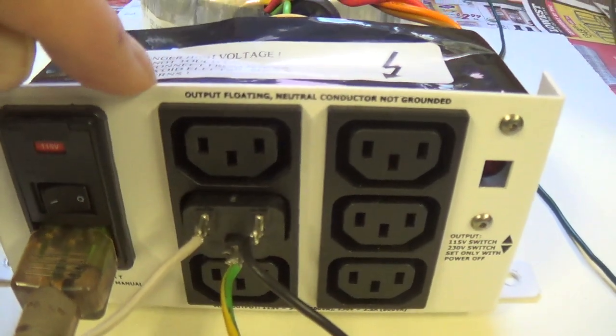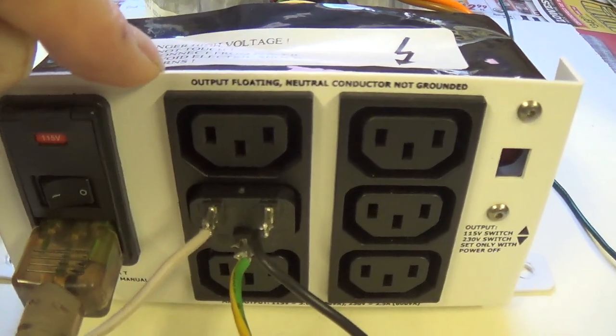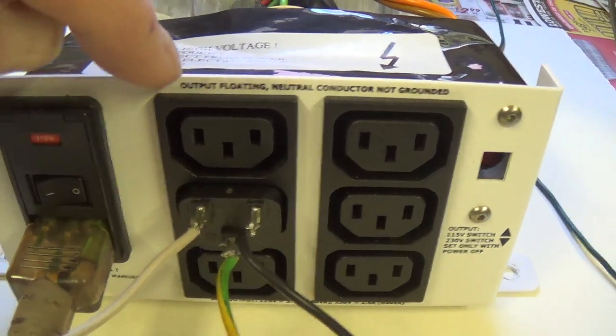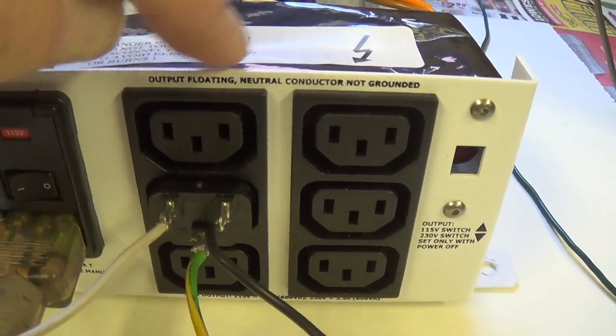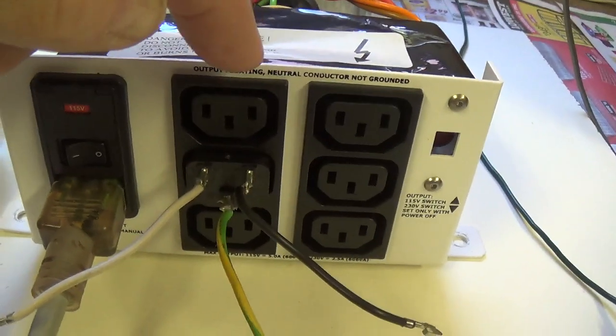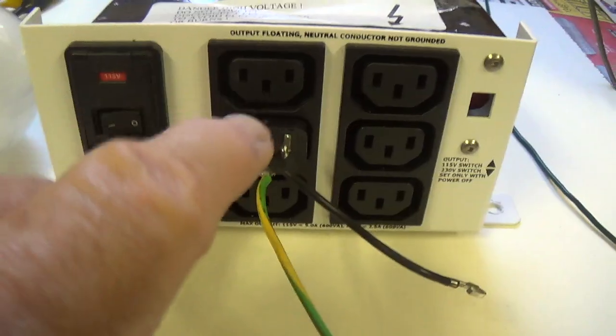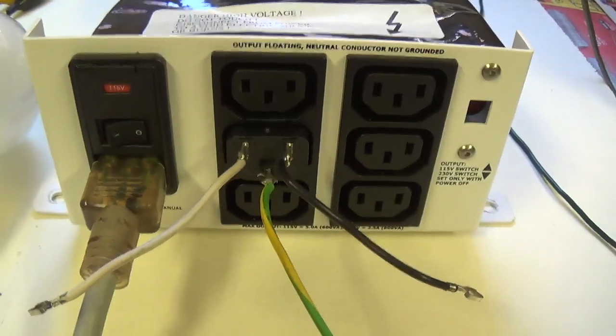However, since this particular medical isolation transformer has the output floating, neutral conductor not grounded, I don't have to do that. It's already been done on this one at the factory, so we can move on now to step 2.